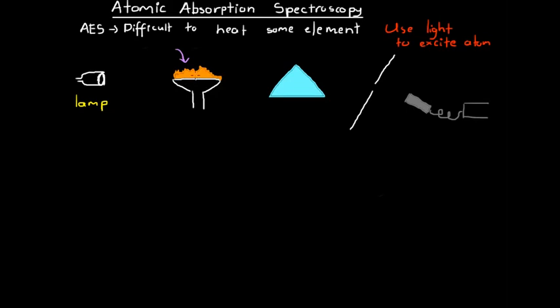The sample gets vaporized in the flame. Light from the lamp passes through this vaporized metal, and certain frequencies of light from the lamp are absorbed by the vaporized atoms as they become excited. As a result, not all frequencies of light make it through the flame. We then measure and analyze the light leaving the atomic vapor using a monochromator.